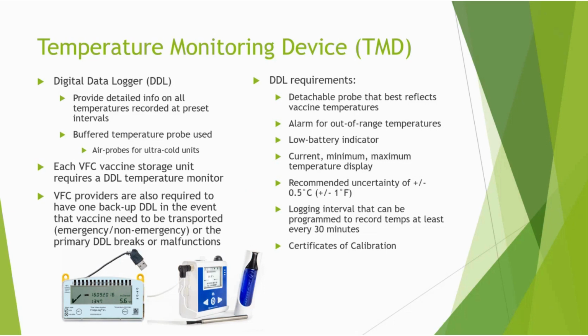Most DDLs use a buffered temperature probe, which is the most accurate way to measure actual vaccine temps. For ultra-cold units, it's a different probe. An air probe is typically used, so that's a different DDL altogether. DDL data is required to be kept for at least 3 years, along with all other VFC-related documents. VFC providers are also required to have at least one backup DDL with a different calibration date in the event that vaccine needs to be transported, whether it be for planned or unplanned emergency transport, or if your primary DDL breaks or malfunctions.